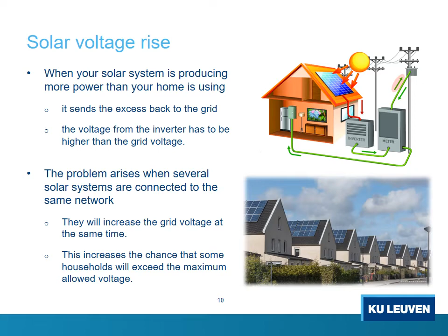The problem arises when, for example, half the people on your street have solar systems too. Every system is lifting the grid voltage at the same time. Then the voltage will keep getting higher and higher. This increases the chance that some households will exceed the maximum allowed voltage, especially around midday on a sunny weekday with high generation and low consumption.